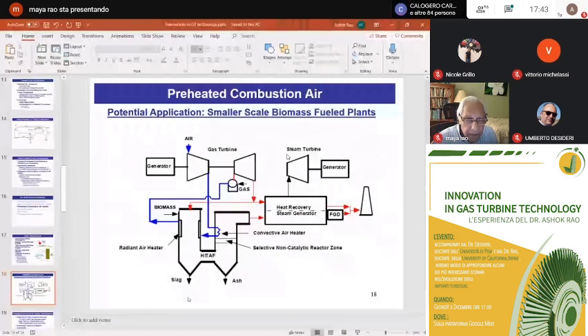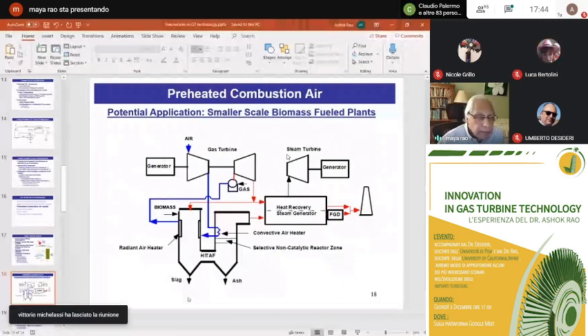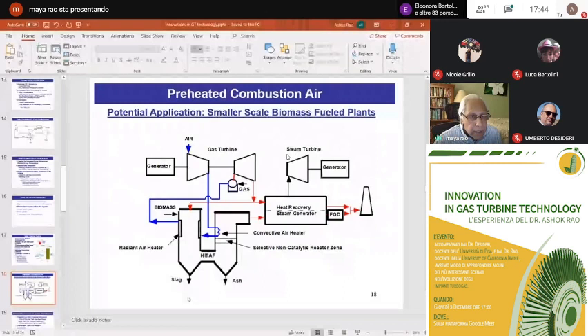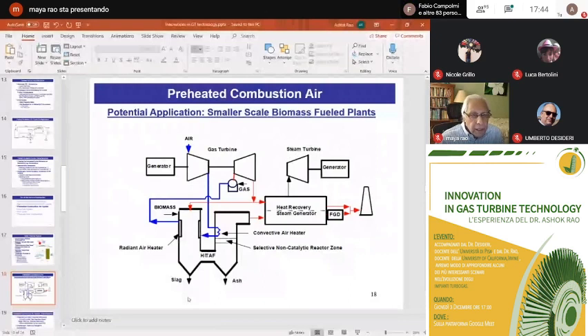This biomass-based system was evaluated in a project funded by the US Department of Energy. They found that the overall cycle heat rate — the amount of fuel needed to produce a unit of power — was 10 to 20% lower than simply using a boiler for the biomass, as in a simple Rankine cycle. Of course, it depends on how much natural gas is burned in the system along with the biomass, and the natural gas used was, in terms of energy input, less than 5%.